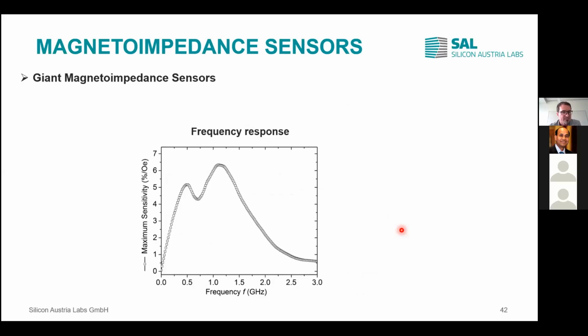Another interesting feature is that the sensitivity is high — we get a strong percent-per-Oersted response. So we have a sensor that can easily detect changes in the Earth's magnetic field, for instance. The sensitivity depends on the frequency, and we can measure at very high frequencies compatible with ISM bands, giving really high sensitivity that allows us to use wireless operation.